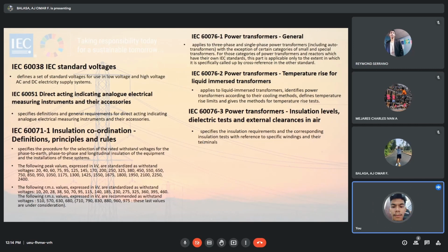Next is IEC 60071-1. Insulation coordination, definitions, principles, and rules. In this standard, it shows the peak values expressed in kilovolts that are standardized to withstand these voltages: 20, 40, 60, 75, 95, 125, and so on. The second is the following RMS values expressed in kilovolts that are standardized as withstand voltages: 10 to 460. The following RMS values expressed in kilovolts are recommended as withstand voltages: 510 to 680. So their unit is kilovolts.